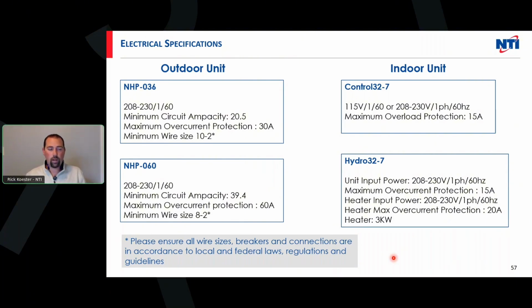Indoor units, on a control, I'm going to say it's going to be 115 volts most of the time. That's the way I'm educating guys. That's the way I wanted them to power this up. We can do dual voltage. I don't know if there's a big benefit there, but if a contractor had a 208, 230 circulator option he was using, that would probably be the only reason why, because whatever we input to the machine, we send out. So if I brought 115 volts in, which is going to be the most common, all my circulator outputs, my auxiliary outputs, stuff like that are all going to be 115 volts going out.